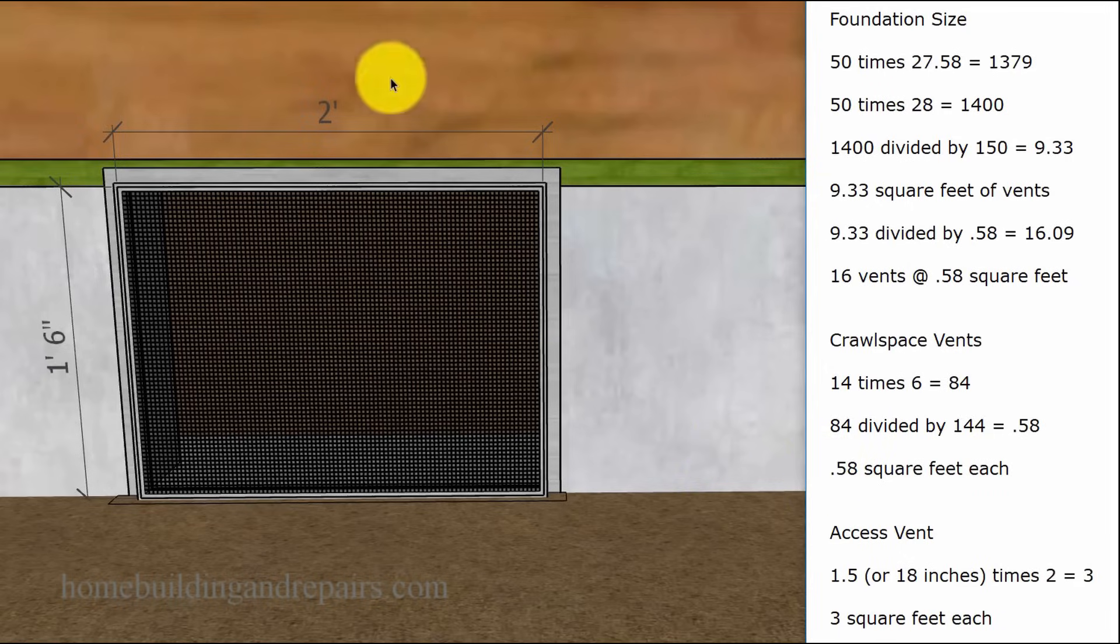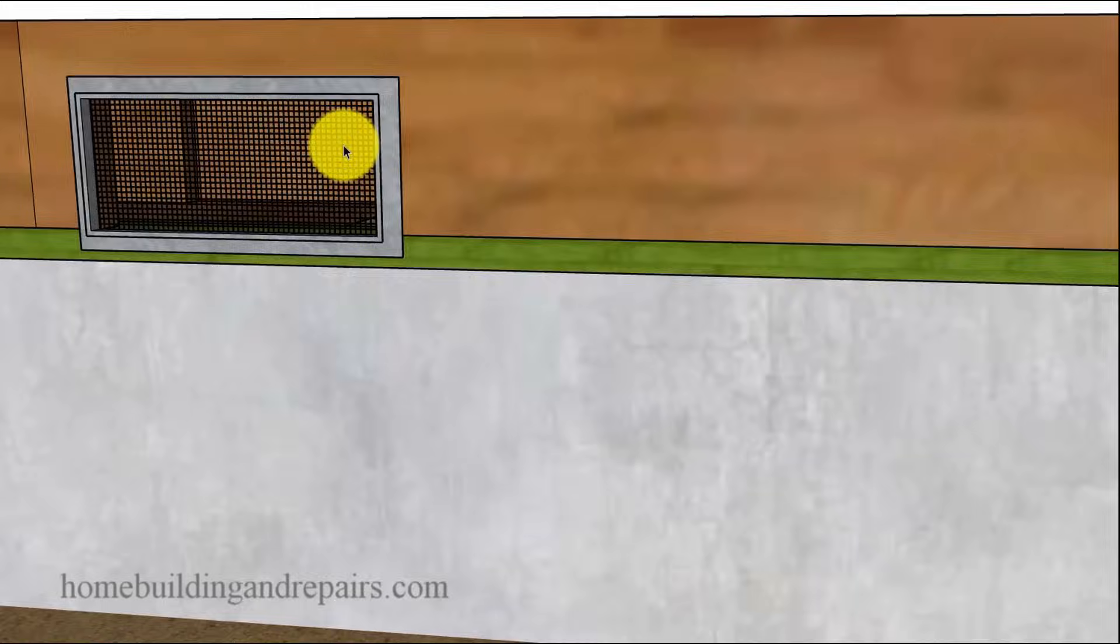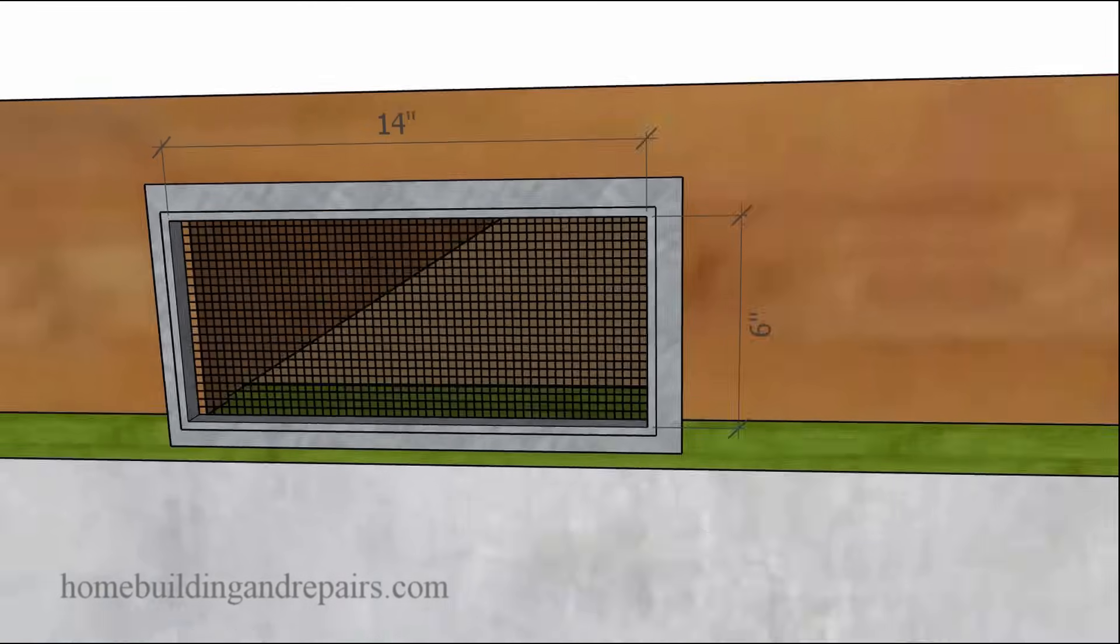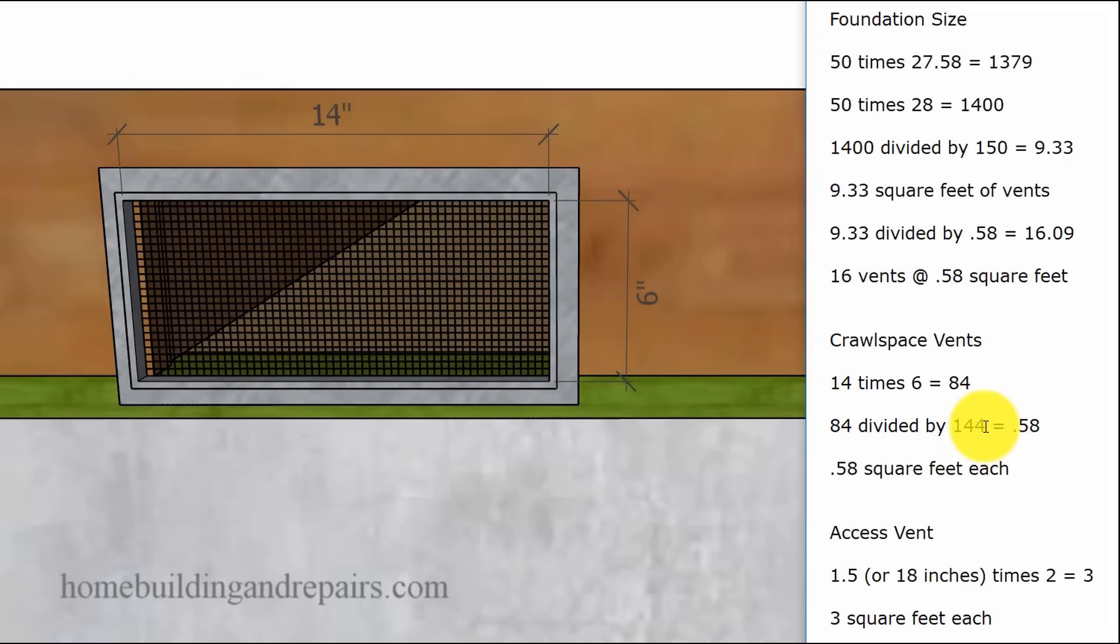And to figure out the crawlspace vent, we're simply going to multiply 14 times 6, going to give us 84 square inches. There is 144 square inches in a square foot.